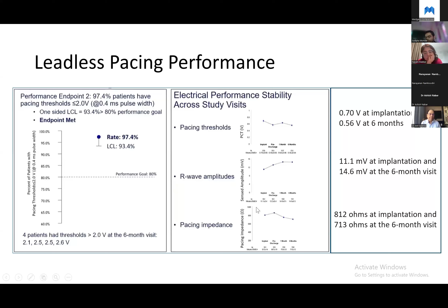So now comes the question of wireless communication. The ICD has to communicate with the leadless pacing system, and this is a system which has unidirectional communication. That means the ICD will communicate with the leadless pacing system, not vice versa. So for wireless communication, the performance goal was 88%, which was achieved. 98.8% had communication success. That means there was no communication failure between the subcutaneous ICD and the leadless pacing system.